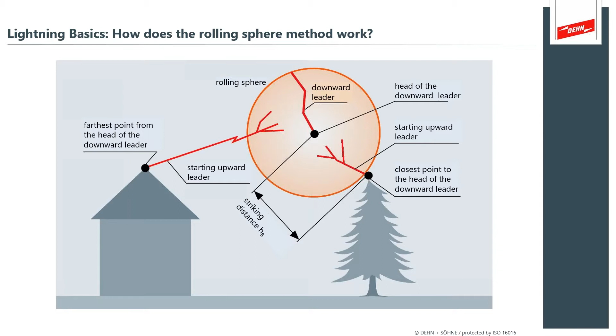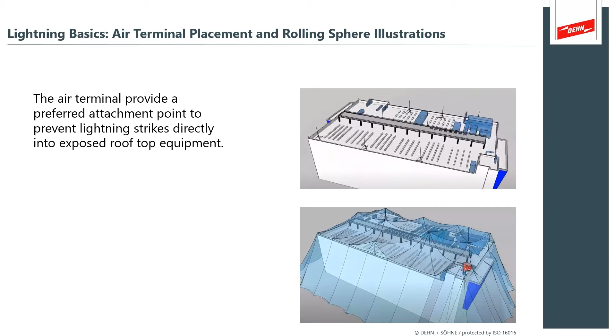So, lightning basics: the air terminal placement over a building is intended to provide a preferred attachment point to prevent lightning strikes directly into exposed equipment. If you had no lightning air terminals, lightning would randomly attach to something that looks attractive, sending off its tendril. The lightning air terminal gives you a chance to safely direct that lightning away from your structure and high value assets. That rolling sphere illustration looks like a tent canopy, almost like a blanket of coverage over the top of your building.